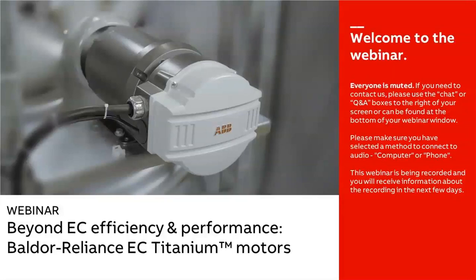Okay. And then what's the full voltage range on the motors? Is it different per horsepower? Was the question specific to the motor only, or the voltage for the whole platform? Okay, on the motor only, it's 230, 460, and keep in mind on the motor only, every one of these has to run on a drive. So the drive itself is going to be the mitigator on voltage tolerance, and our drives have the same voltage tolerance as most drives out there. For example, on a 460 volt drive, it might be 380 plus or minus 10% up to 480 volts.